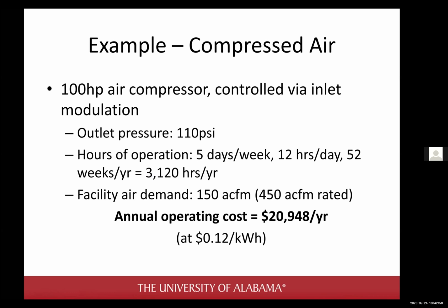However, in looking at the data we got from analyzing the amperage going into this compressor, we figured out that they were only using 150 cubic feet per minute on average. And that'll become important later. Regardless, by looking at the kilowatts and the kilowatt hours going to this machine, we estimate it was costing them about $21,000 a year to run this 100 horsepower air compressor. So it costs about $21,000 a year to run the compressor, and they use about 1/3 of what the compressor could give them, which doesn't seem that bad.